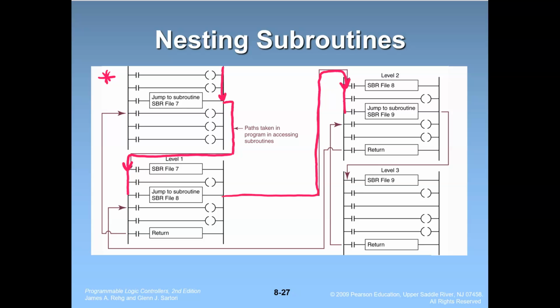So something to remember, this nesting of subroutines can affect the scanning rate significantly, and it may cause input and output not to be evaluated at the required time. It can make the scanning time so long that the data that you need to constantly update remains unupdated, and it makes some problem for your application.